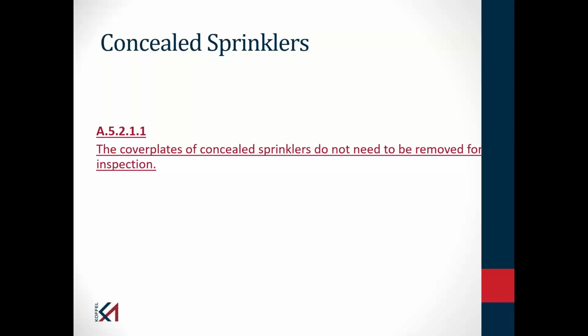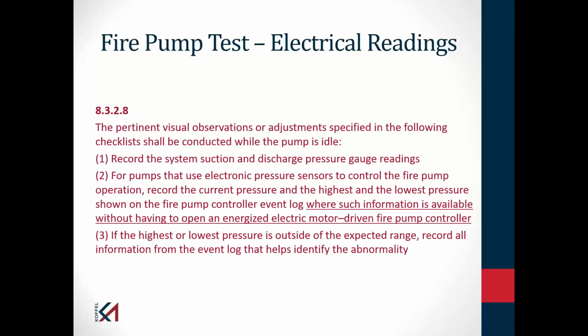I would not be surprised if the committee comes back and revisits this as we are entering into the 2023 cycle, because I am hearing of increased incidents of people finding concealed sprinklers that are corroded. So if you have them and you suspect that the environment might cause corrosion of the sprinkler, again, while not required by NFPA 25, you may want to investigate whether you have corrosion on those sprinklers.